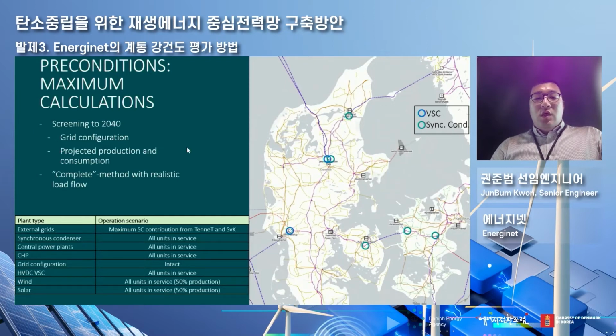When we do the maximum calculation, we consider synchronous condensers or central power plants, external grid, CHP, grid configuration, HVDC, VSC in full operation, and wind and solar, all units in service. Because of the intermittent characteristic, based on our experience, we come up with a scenario where wind and solar make a contribution of 50%.